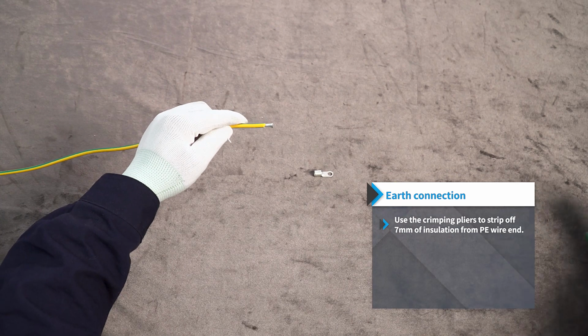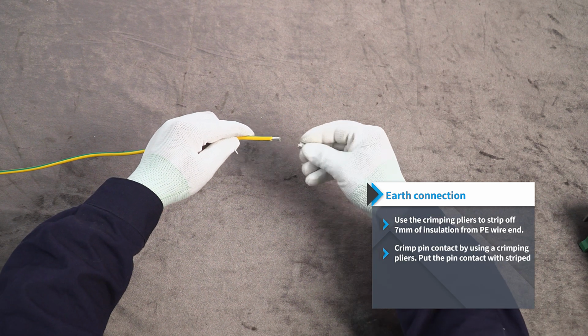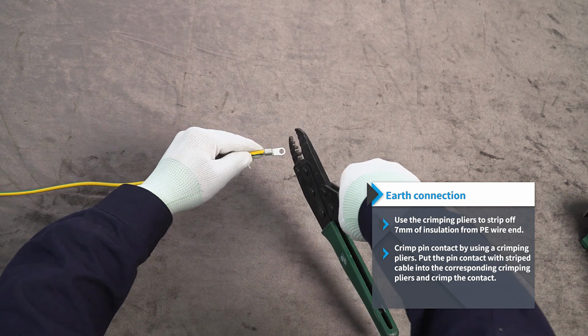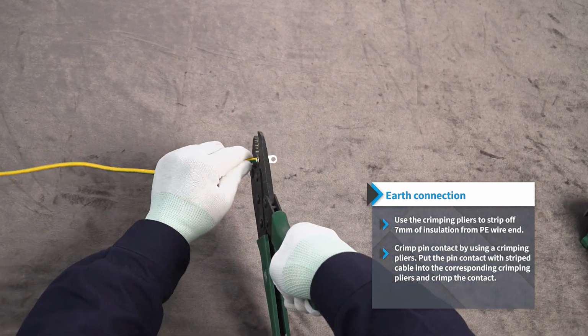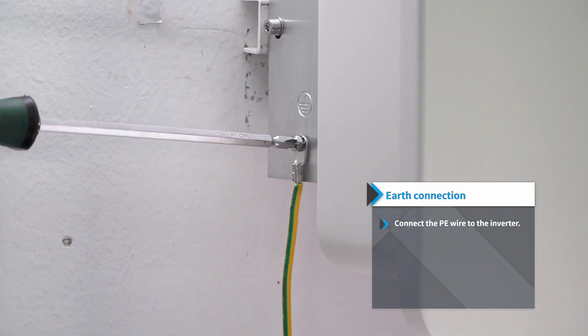Earth connection. Use the crimping pliers to strip off 7 mm of insulation from PE wire end. Crimp pin contact by using a crimping pliers. Put the pin contact with stripped cable into the corresponding crimping pliers and crimp the contact. Connect the PE wire to the inverter.